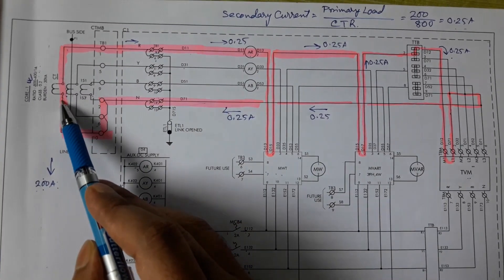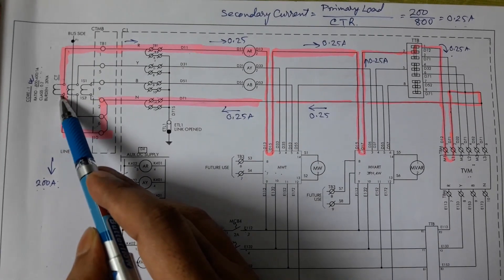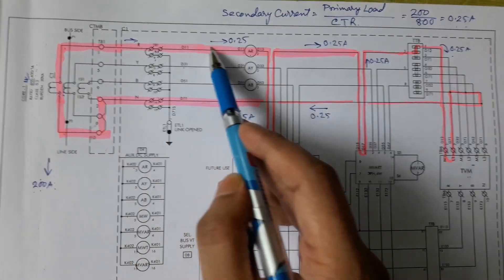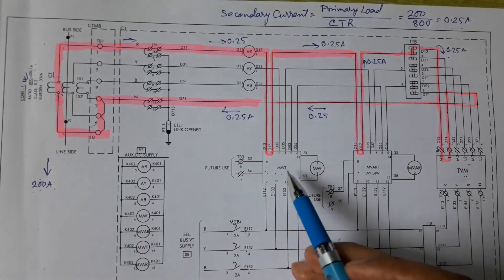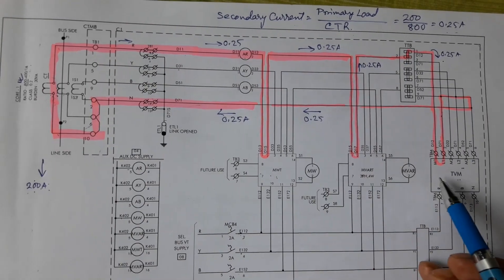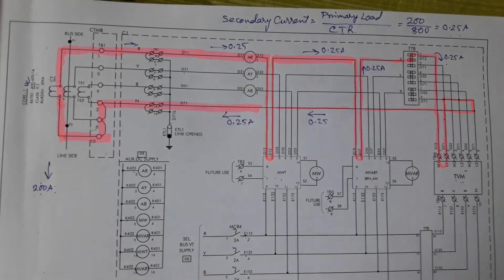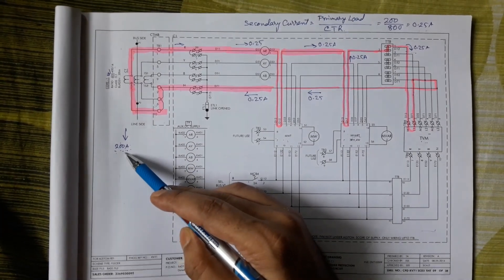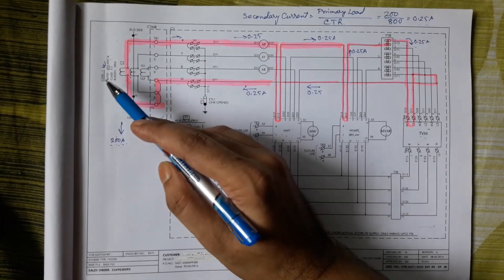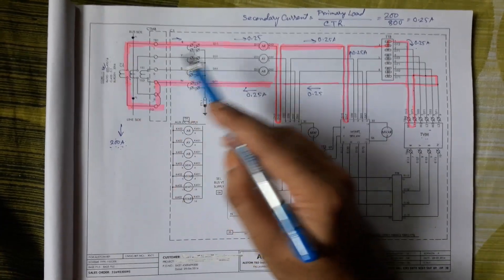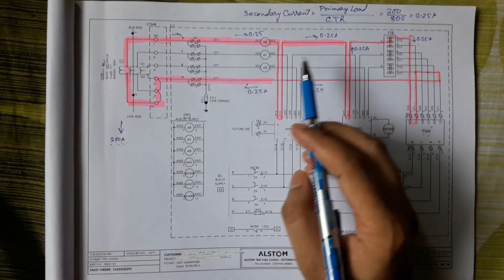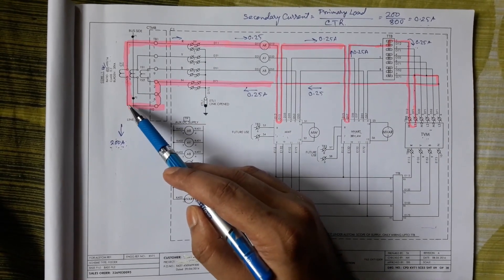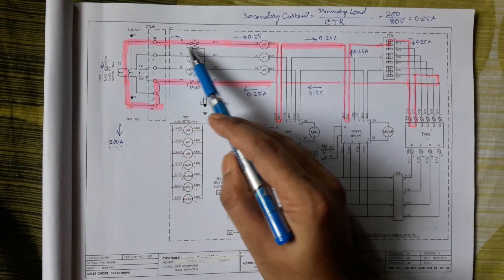For simplicity, we will discuss only the red phase CT. Notice that the red phase CT is connected with 1 ammeter, 1 megawatt meter, 1 megavar meter, and 1 trivector meter or energy meter. Suppose the load current of the CT primary is 200 ampere. As the CT ratio is 800 by 1, the secondary current will be 0.25 ampere, and this 0.25 ampere will follow the shaded path.